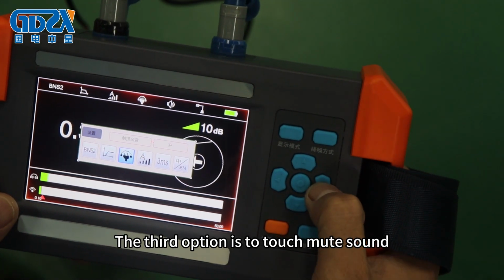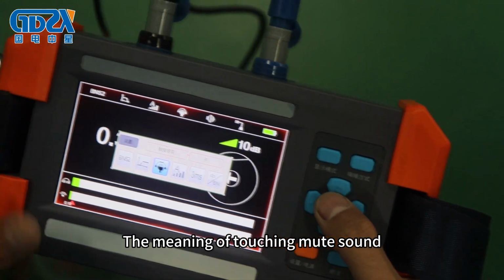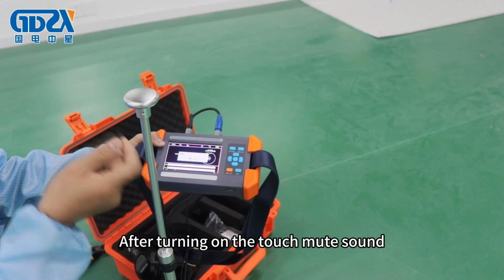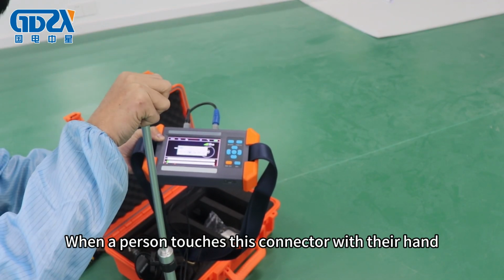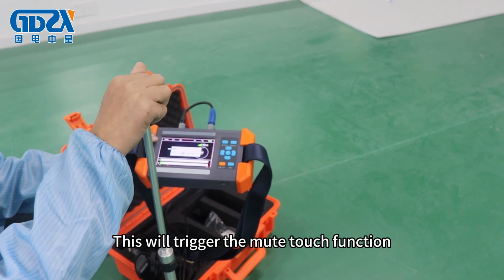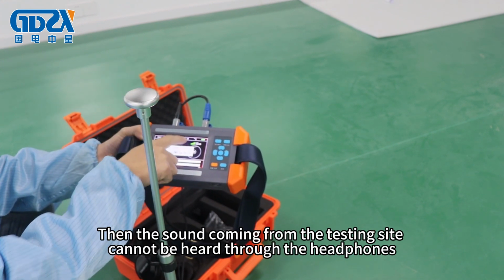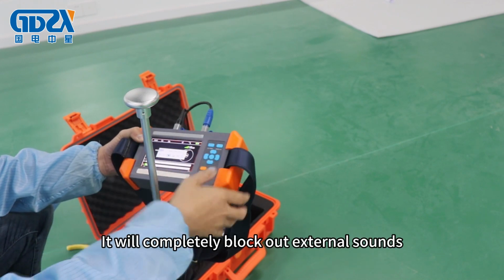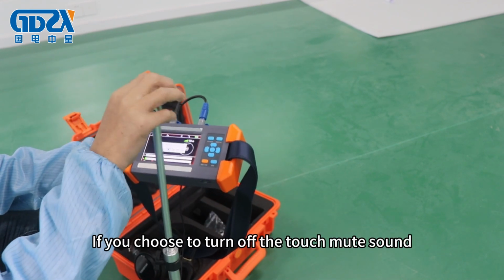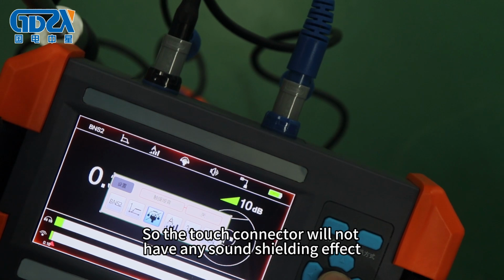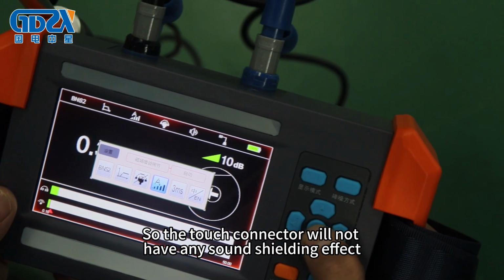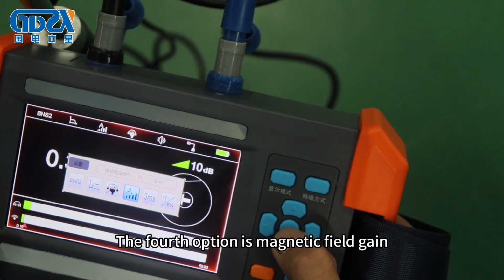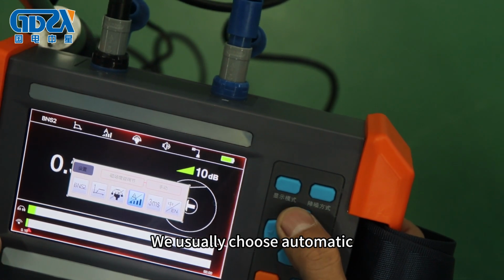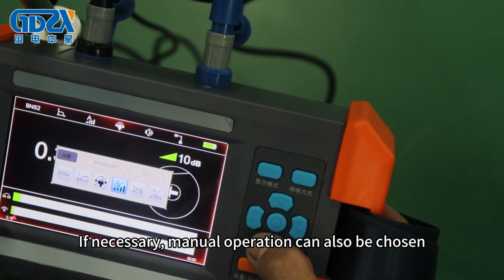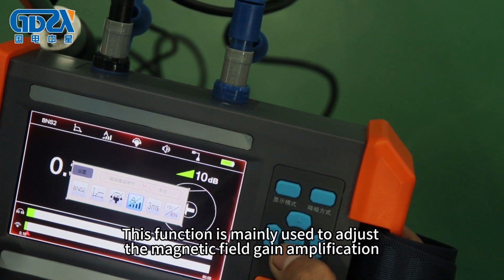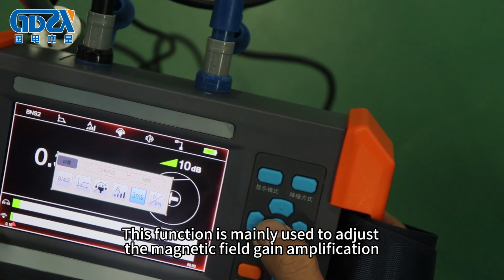The third option is touch mute sound. The meaning of touching mute sound. After turning on the touch mute sound, when a person touches this connector with their hand, this will trigger the mute touch function. Then the sound coming from the testing side cannot be heard through the headphones. It will completely block out external sounds. If you choose to turn off the touch mute sound, the touch connector will not have any sound shielding effect. The fourth option is magnetic field gain. We usually choose automatic. If necessary, manual operation can also be chosen. This function is mainly used to adjust the magnetic field gain amplification.